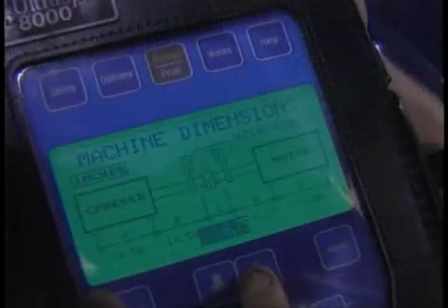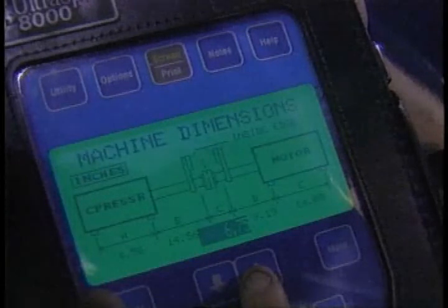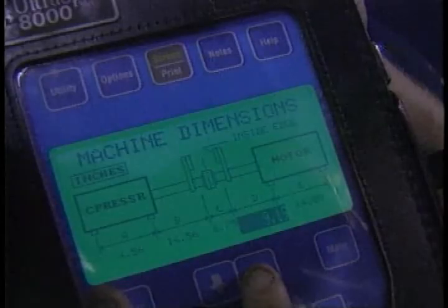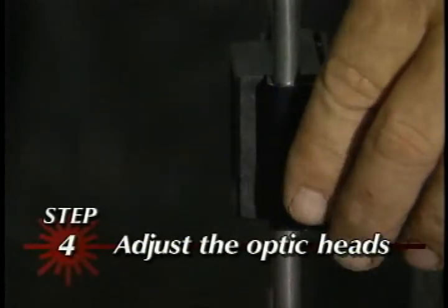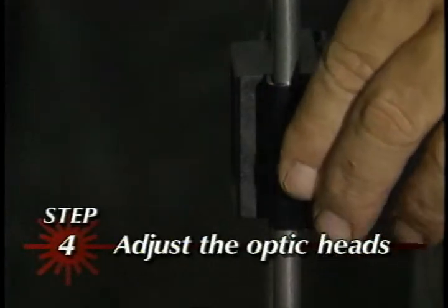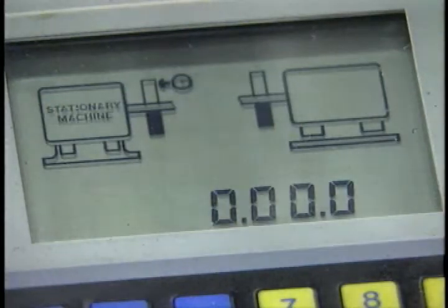Now, not all laser alignment equipment will ask for this exact list of measurements, but the list will be quite similar. Step 4, make final adjustments to the optic heads. Although they all work slightly differently, alignment computers will typically display X and Y coordinates representing the position of the beam on the detector. If the beam is centered, the coordinates will be 0, 0.